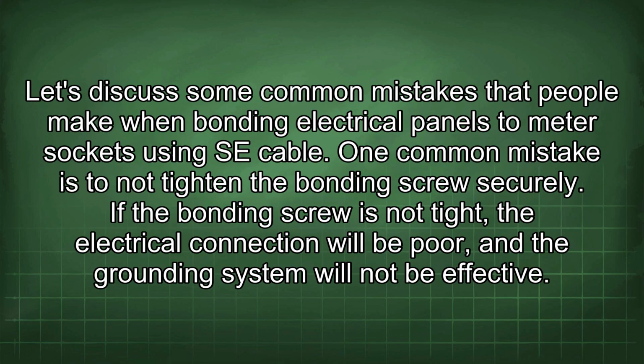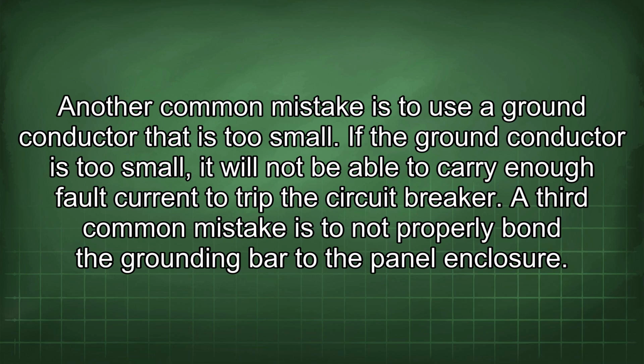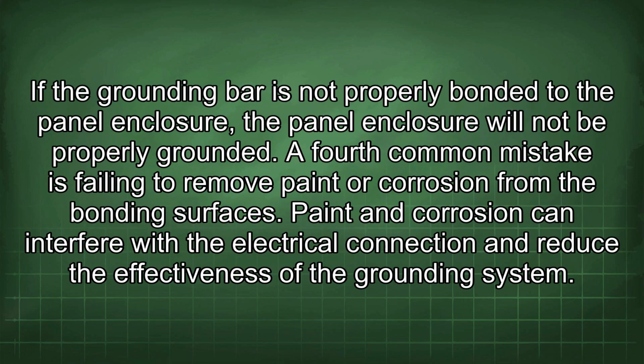Let's discuss some common mistakes that people make when bonding electrical panels to meter sockets using SE cable. One common mistake is to not tighten the bonding screw securely. If the bonding screw is not tight, the electrical connection will be poor, and the grounding system will not be effective. Another common mistake is to use a ground conductor that is too small. If the ground conductor is too small, it will not be able to carry enough fault current to trip the circuit breaker. A third common mistake is to not properly bond the grounding bar to the panel enclosure.